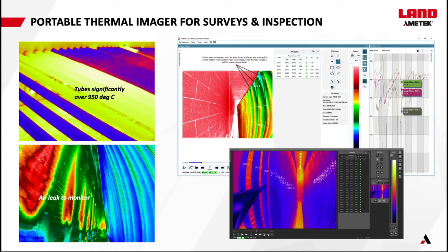The bottom right-hand side image is something I like to use for training a lot. It shows the gold cup being inserted. So you can see that we've put the gold cup on that third or possibly fourth tube. And it's interesting as well. It shows how effective the cooling of the gold cup is, because you can see the very low temperature of the gold cup itself. But actually, interestingly, that gold cup surface is polished. So we do see reflections of other tubes. So the gold cup surface temperature may look high, but that's because it's seeing reflections of other tubes. So it's a nice example of incident radiation.